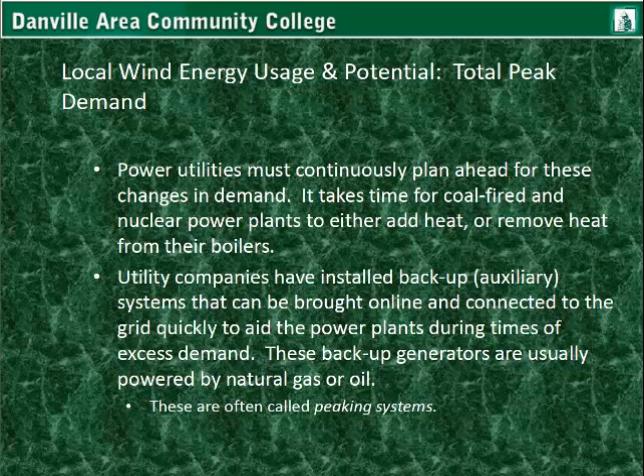Power utilities must continuously plan ahead for the changes in demand. It takes time for a coal-fired power plant or a nuclear power plant to add heat or remove heat from their boilers. Utility companies have installed backup or auxiliary systems that can be brought online and connected to the grid fairly quickly, in case there's excess demand. These backup generators are usually powered by natural gas or oil, and they are often called peaking systems.